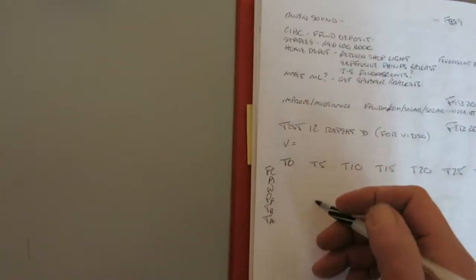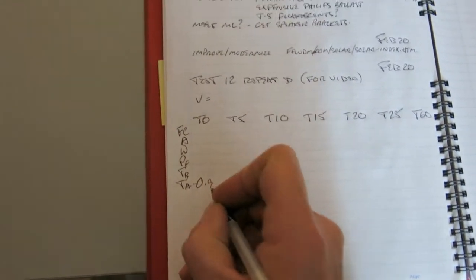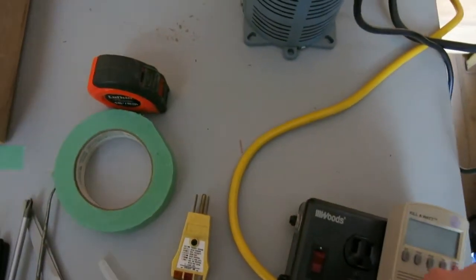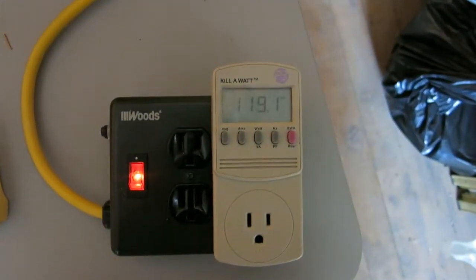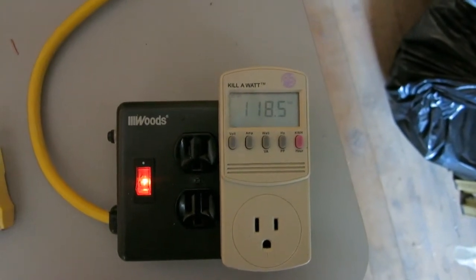Let's begin — I have my pen behind my ear because it's so cold. Let's start by recording the room air temperature and the ballast temperature. This meter is a Kill A Watt meter. We're going to record the voltage. Voltage is actually fairly high right now — 118.5 volts. I found that these lamps aren't too sensitive to the voltage.